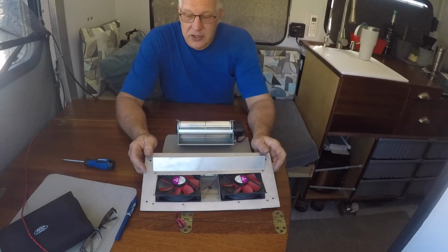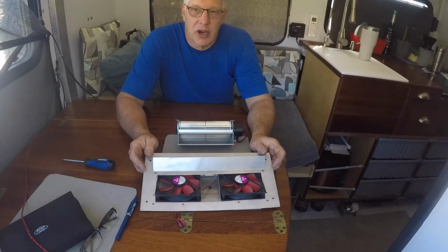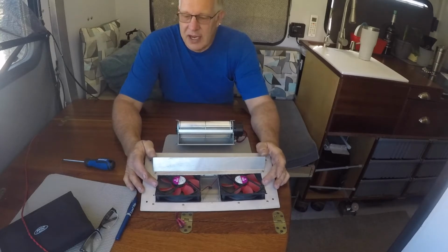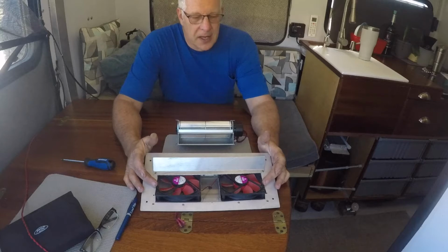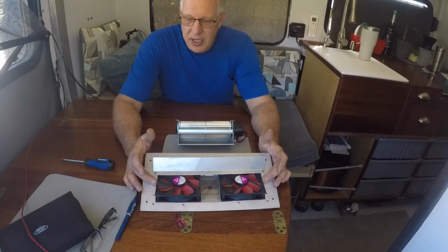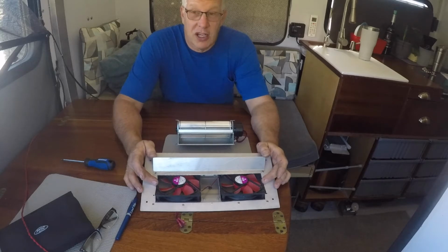air. So static pressure is required to move air through a duct which has resistance. In order to cause a certain amount of airflow to happen, you have to create a certain amount of static pressure. These fans here, although they can move quite a bit of air in free space, they are not the style necessary for a duct. These fans only produce about a half an inch of water column of static pressure.